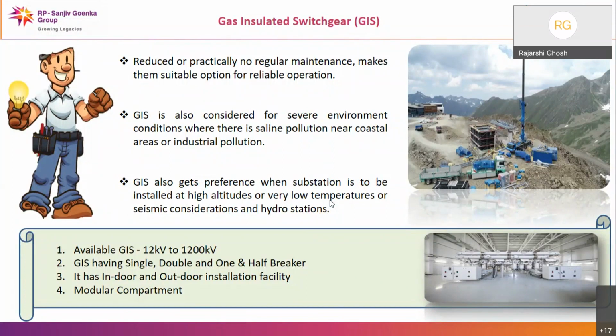GIS is available from 12 kV to almost 1200 kV. All the voltage ranges are available. It has single, double, and 1.5 breaker systems, single bus, double bus, 1.5 breaker, whatever is required, it can be manufactured. It has indoor and outdoor installation facilities, so it can be installed outdoors also. There is no need for anything, only some shade is required due to the LT panels. And it has a modular compartment, so it is very advantageous to install and maintain.